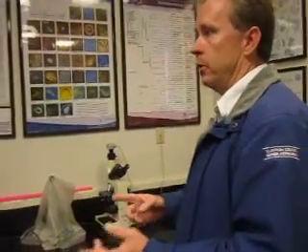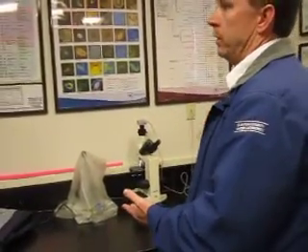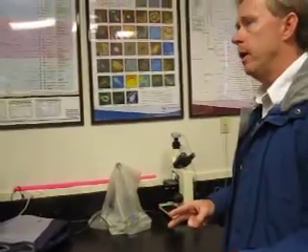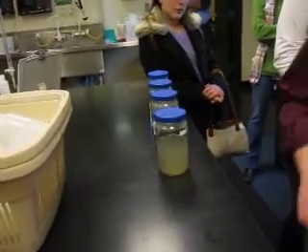The other thing is phosphorus removal. We've got to remove phosphorus as well. It's a nutrient. It causes things to grow out there in the rivers, lakes, and streams, so we want to minimize that before we send the wastewater on its way after we treat it. So how do we do that? We've got two ways of removing phosphorus. It comes into the plant around 7 to 10 milligrams per liter in that raw wastewater. But as it goes through the biological process, there are bacteria, microbes in there that take phosphorus into their cell wall, absorbing the phosphorus.